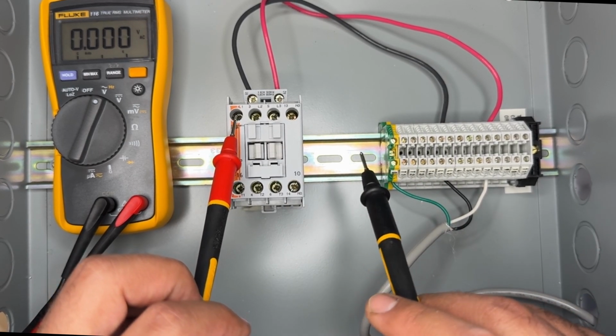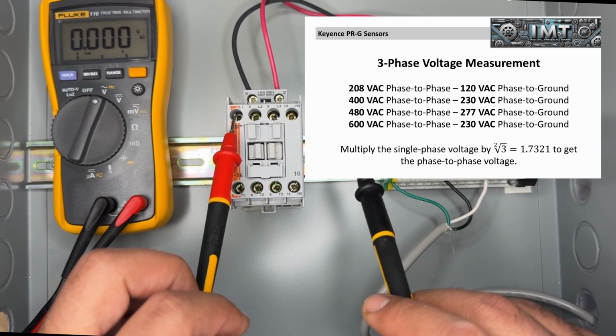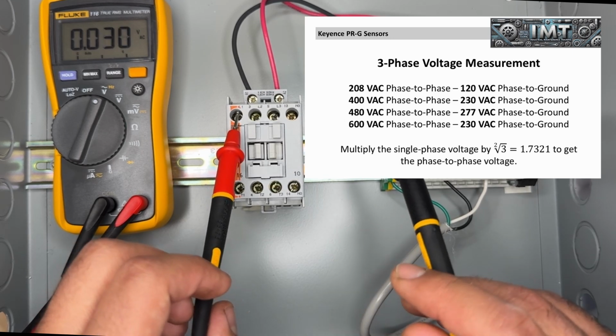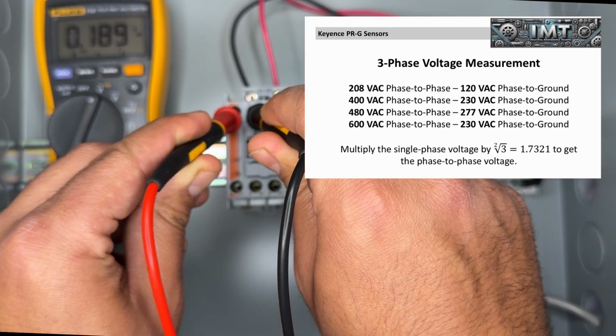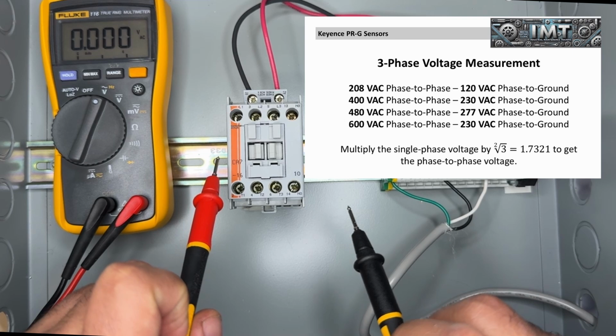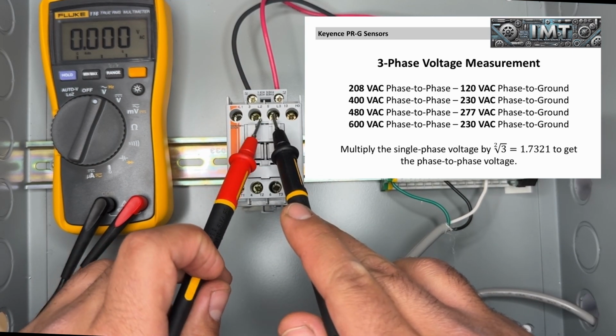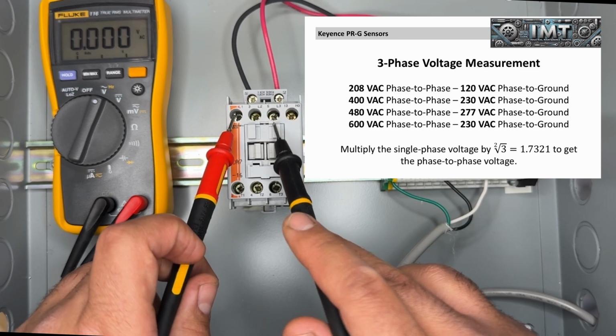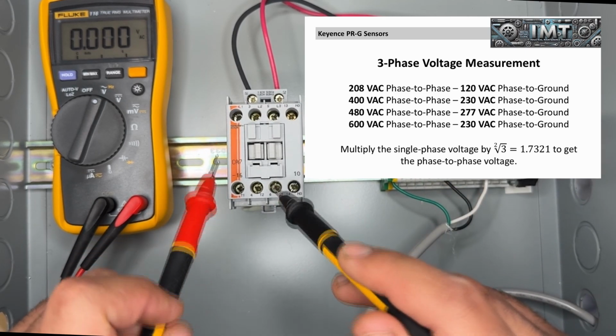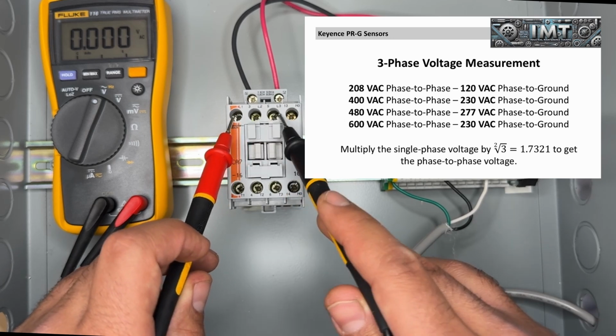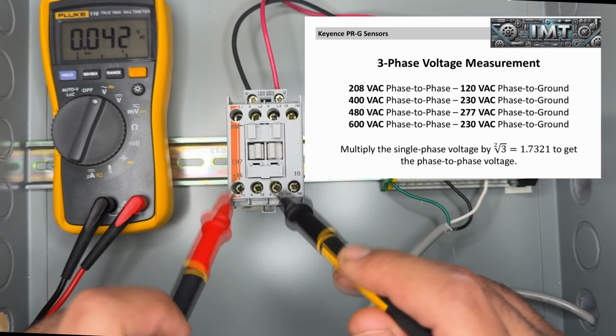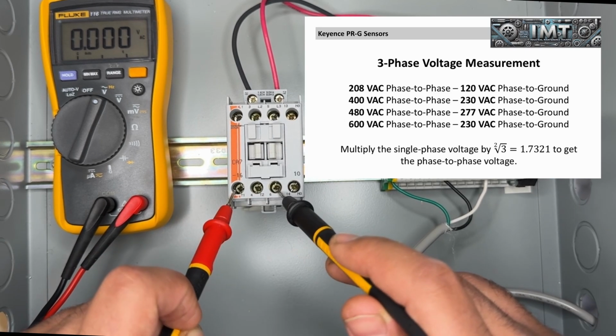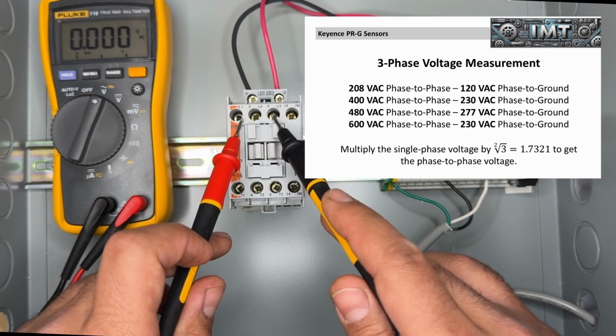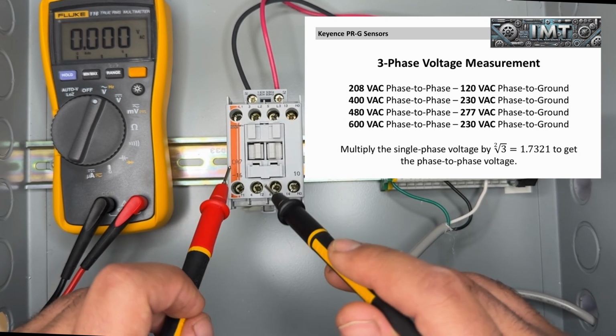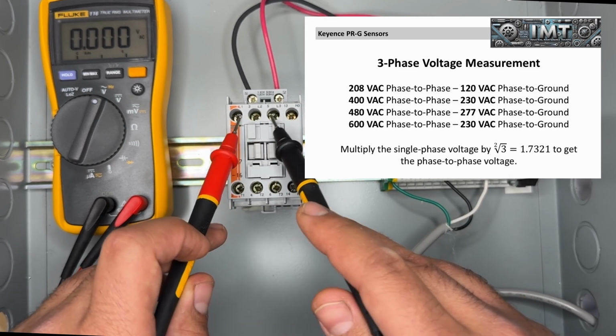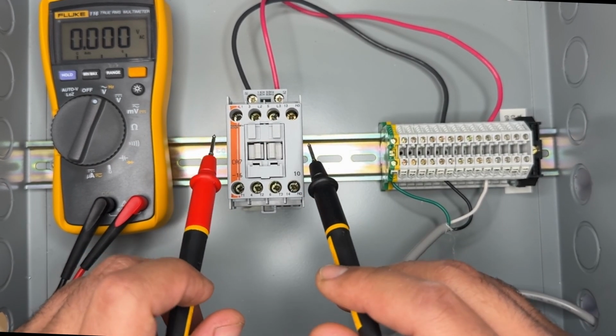And what you're looking for will depend on your particular configuration. If you're running a 600 volt system, for example, you're going to want to see 600 volts phase to phase. We don't have a high voltage applied in this case, but you'll want to see 600 volts phase to phase across each of these two phases, or 347 phase to ground. And what you want to do is make sure you have the right voltage across the top three terminals. And then if you have your voltage there, check for the voltage underneath, see if you have it there as well. If you see it on your line side but not on your load side, that could indicate an issue with your contacts. If you're not seeing it at all on your load side either, then that could indicate a different issue in your panel.